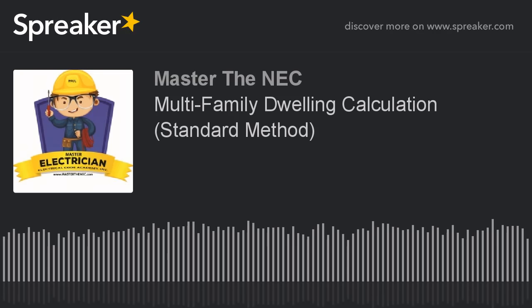21,168. Now, since this air handler was 120 volts, we're going to have neutral load as well. And that's just going to be the exact same value. So under the neutral column, I write 21,168, and that's the value that's going under our neutral column as well. Okay, so you should have all these things adding up in your columns.